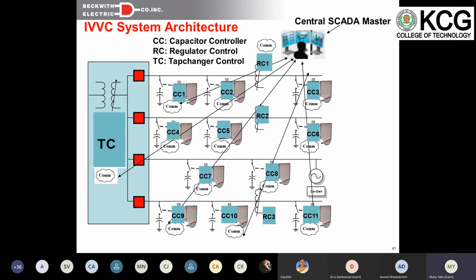So if you look at a typical Volt-VAR control system, you've got a substation and a transformer that has a tap changer. The tap changer's main purpose is to adjust the taps in such a way as to keep the voltage in India at around 230 volts to all the customers. If the load increases, the voltage goes down, and the tap changer increases the tap. If the load decreases, the voltage goes up, and the tap changer decreases the tap, so that customers are always getting around 230 volts plus or minus 5%.